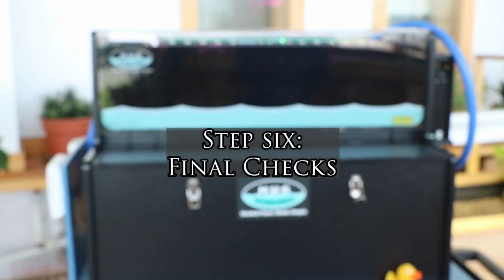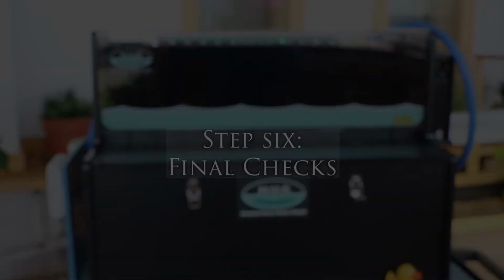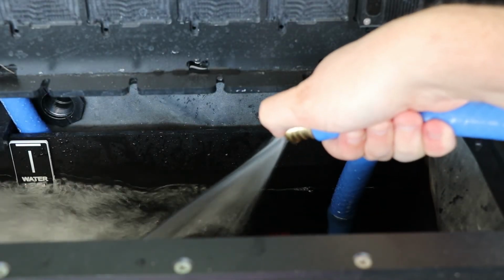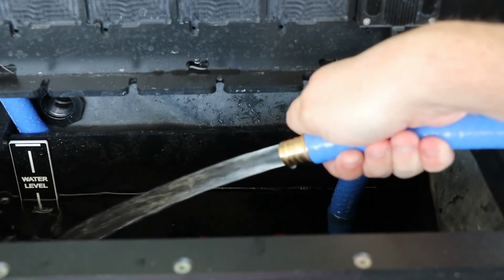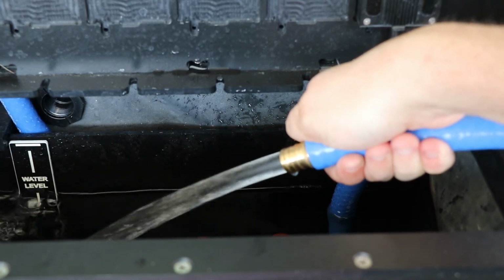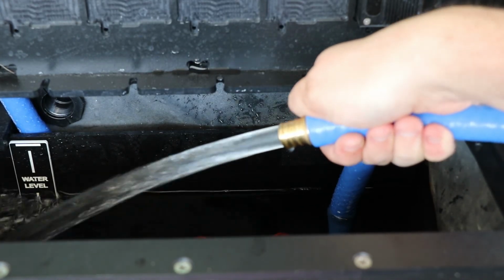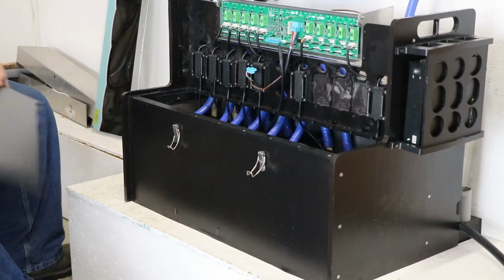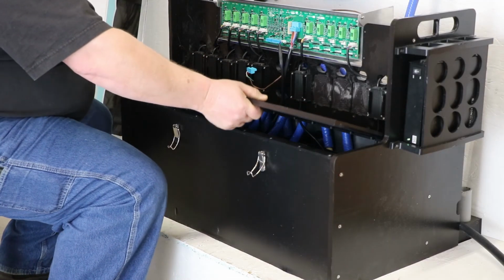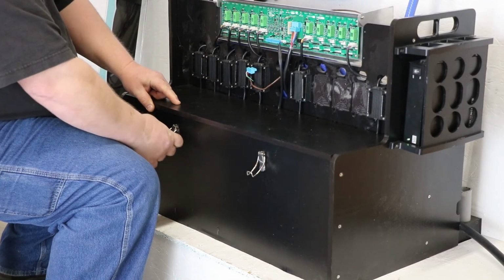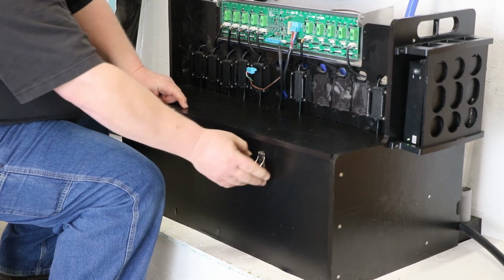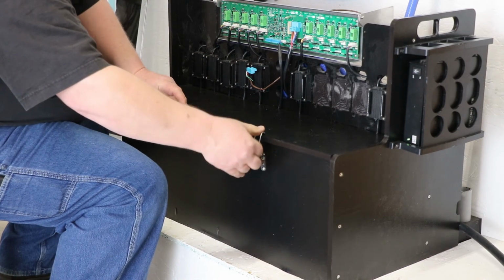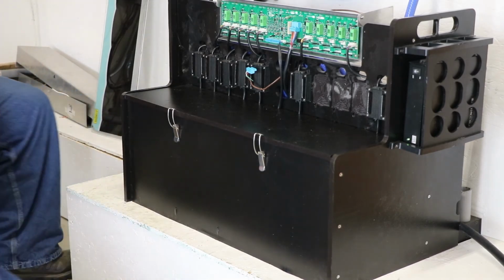Step 6. Final checks. Check the water level. Add additional water or glycol mix until you reach the upper mark of the water level indicator. As a note, we recommend adding a calendar reminder to check the water level every 6 months. Reinstall and latch the tank cover. Caution, the water may be hot.